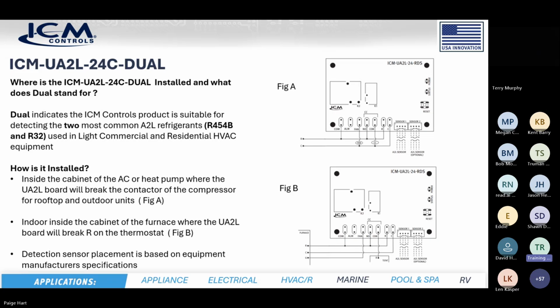We wanted it to cover the two most common A2L refrigerants used in the market, which are R454B and R32. These are the most common A2L refrigerants used in light commercial and residential HVAC. The boards we make for the OEMs can use whatever A2L refrigerant they want, and they pick the sensor they want. But for the aftermarket, we asked what the most common ones are, and we came up with this sensor that can sense the two most common A2L refrigerants out there. This makes this board good for the aftermarket.